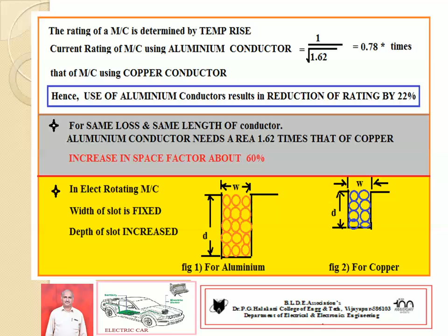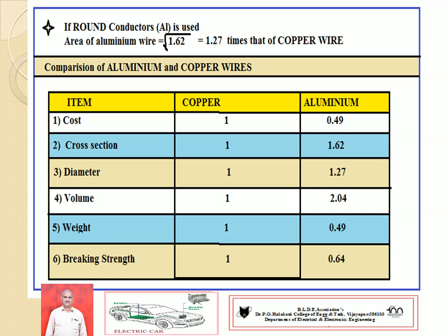Similarly, if round conductors of aluminium are used, then the required size of wire should be equal to 1.27 times that of copper wire. Hence, keeping copper as the standard, what changes occur in aluminium? This table gives the comparison: if the cost of copper is 1, the cost of aluminium is 0.49. If the cross section of copper wire is 1, the requirement of aluminium is 1.62 times. If the diameter of copper is 1, the requirement of aluminium is 1.27. It gives a complete comparison of copper and aluminium, how strong or weak each is. Aluminium is weaker in breaking strength: copper is 1, aluminium is 0.64, that is, less mechanical strength.